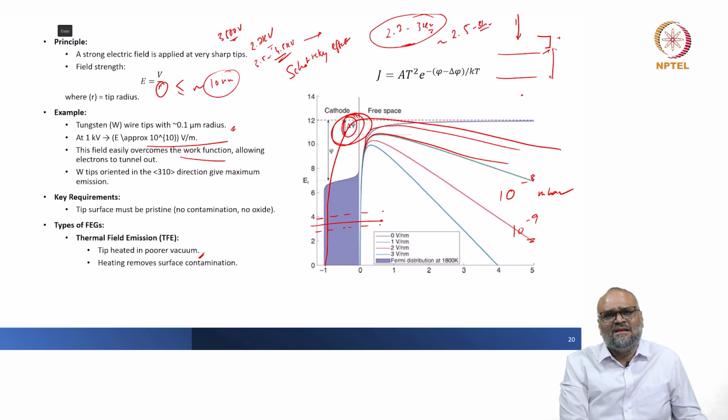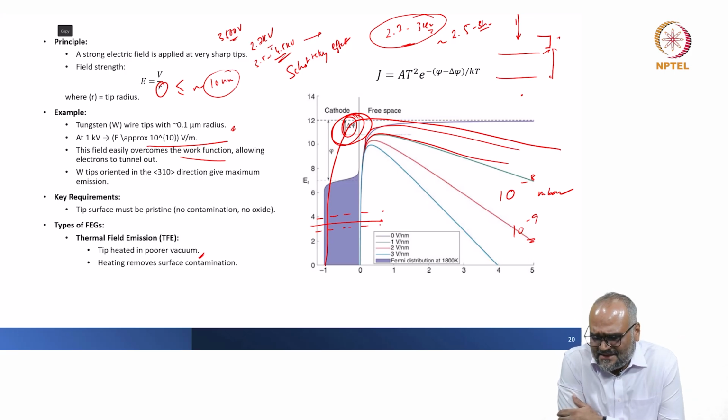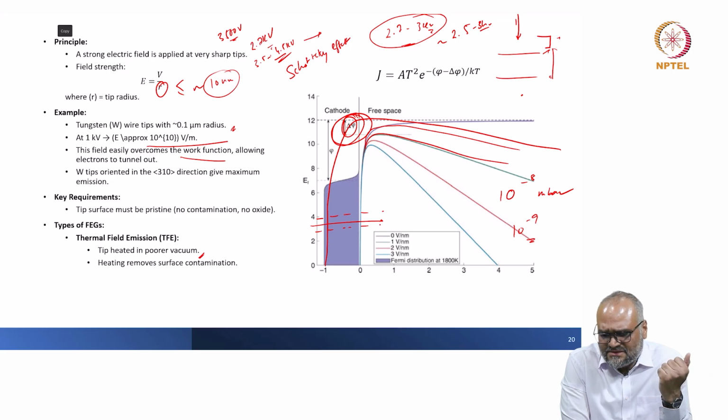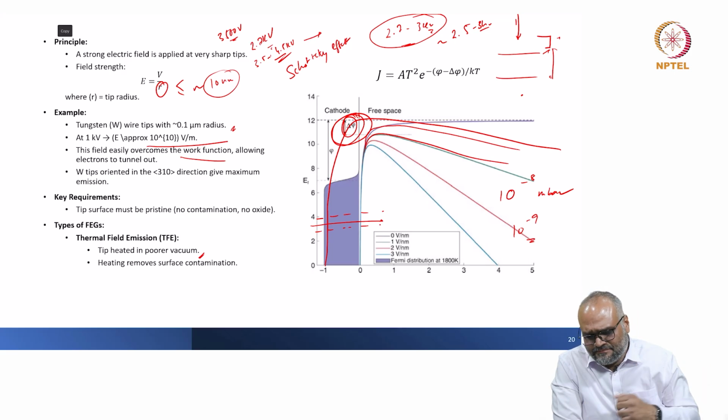In the very old days, on the older instruments like the Philips CM20 or CM30 series, you were manually turning the knobs. With the digitization and having feedback controls, you can now do a warm start in a very gradual way.